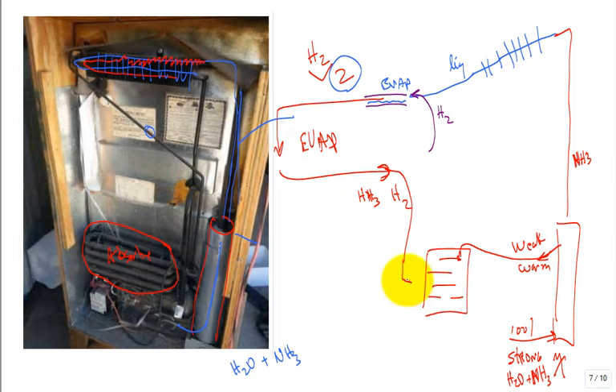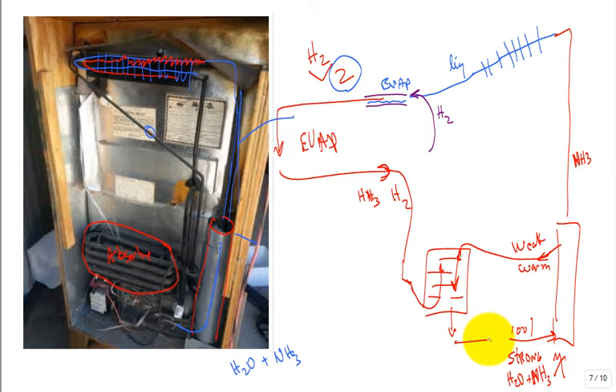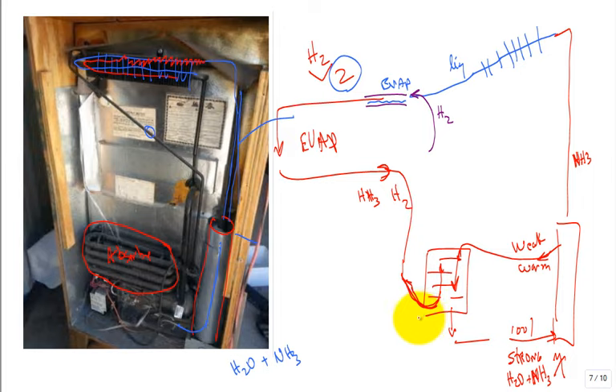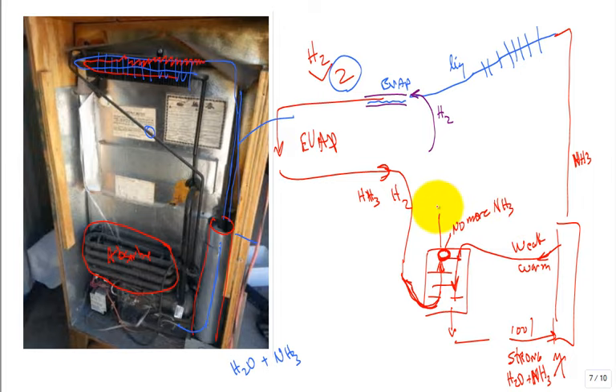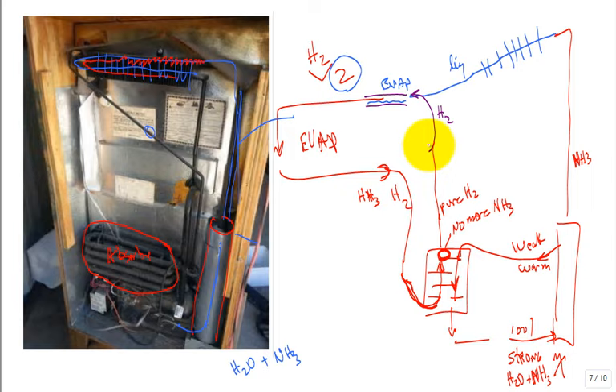The ammonia is pretty strong here, so you want to do a counter-current flow. The weak solution, when it comes out at the bottom, is now back to strong. It's going to be strong if it's in the presence of a really dense ammonia. This is where you have the most ammonia in the vapor state coming in, so you flow those counter-current. When you get to the top here, you'd like to have no more ammonia—just pure hydrogen. The hydrogen is going to loop.